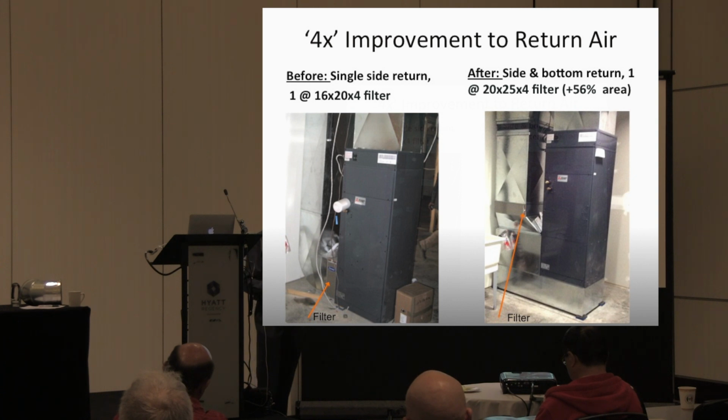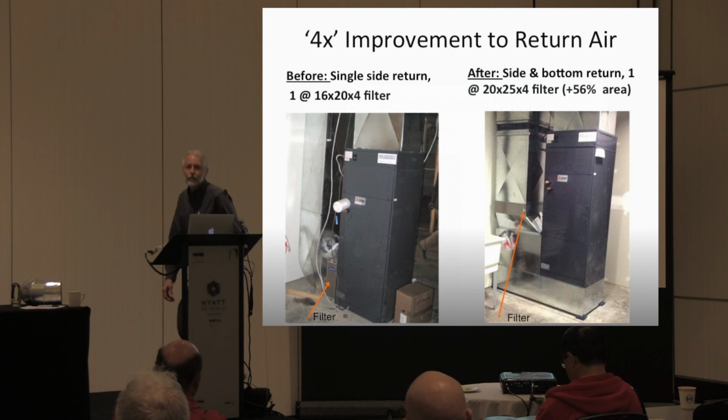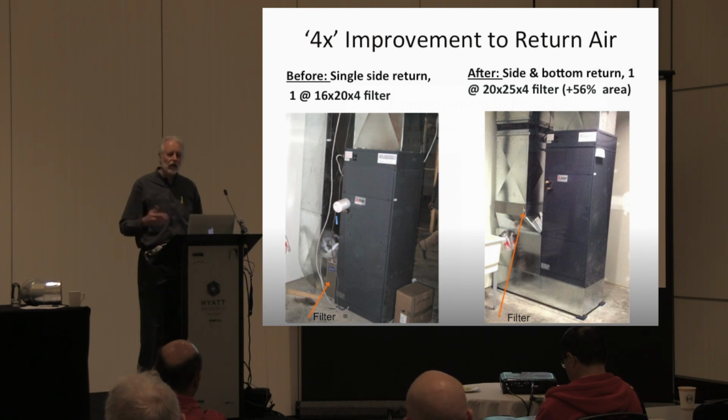I finally got pissed, called my friend who ran Mitsubishi here, and I said, can you apply some pressure? They lost their shirt in this job because this didn't even meet the manufacturer's installation minimums. It's a 3-ton piece of equipment. You can't come in on one side. The manufacturer didn't permit it. They had to lift the thing up, come into the side and the bottom, and put the filter where it should have been, because that's the only way that compressor is going to live. I mean, I shouldn't have to do this kind of shit.